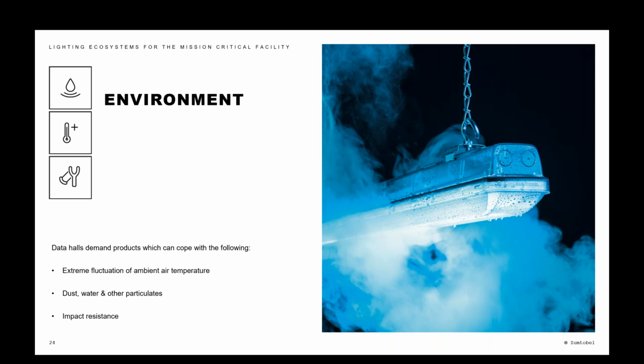And then if you move on to the internals, when you're looking at internal plant areas, you get extreme fluctuations in temperature due to the plant that's in there. Some plant areas may be temperature controlled, which is fine. You need a luminaire with protection against dust, water, particulates, because they're not clean environments generally in a plant area, and you need a level of impact resistance. For an internal plant area, an IK8 rated luminaire, which is the impact resistance, is absolutely fine. These are the kind of things we consider before we even put forward a luminaire choice within that area of the project.